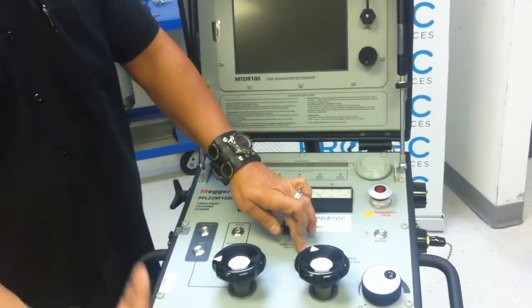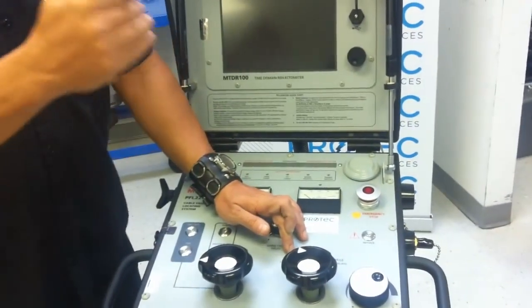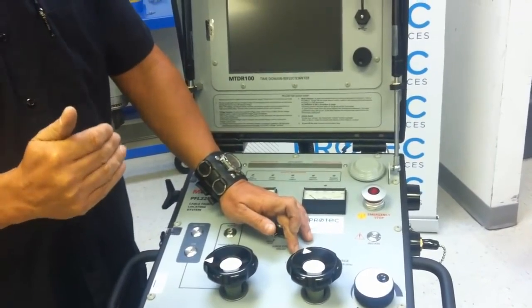Here, energy is what we want to deliver to the fault to get successful breakovers, to get good strong arcs for our radar coupling. What we want to limit is the amount of voltage that we're applying. The voltage is the stressful element, particularly in a service age cable. So in a constant energy thumper, by giving the client the ability not only to adjust output voltage, but to also adjust the capacitance, what we're able to do is on the lower thumping ranges, utilize larger capacitance, deliver maximum amount of energy at the lowest possible thumping values of voltage.